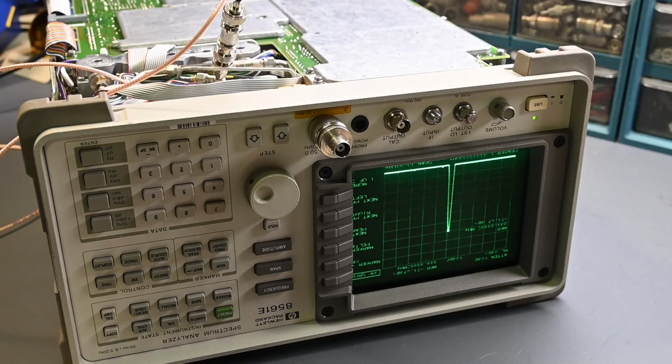So minus 31.67, 1 gigahertz. I was just writing these values down just for reference. And again, no problems there. That's looking perfectly acceptable. I'm not seeing any problems. So I think the switch and YIG tune filter is likely where the problem is. But again, I'm going to measure the voltage on the drive to that switch just to make sure that those values are correct. So I'll do that next.